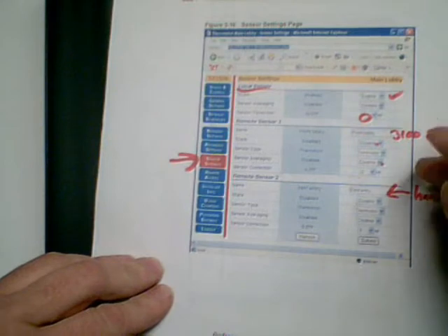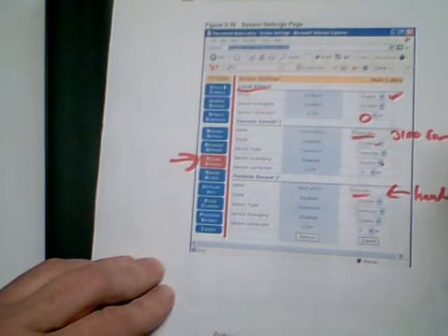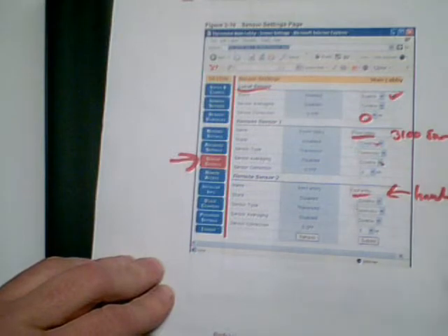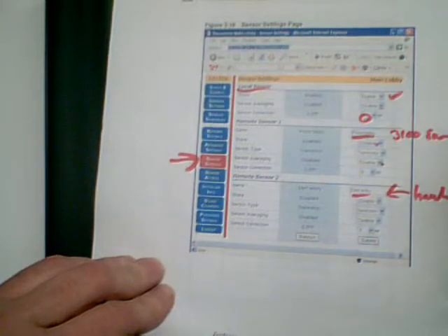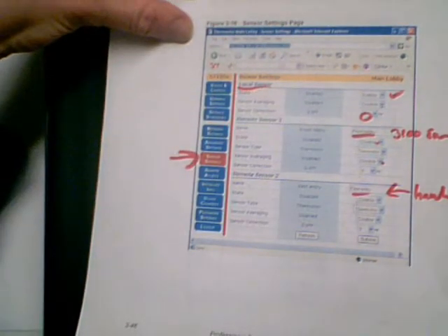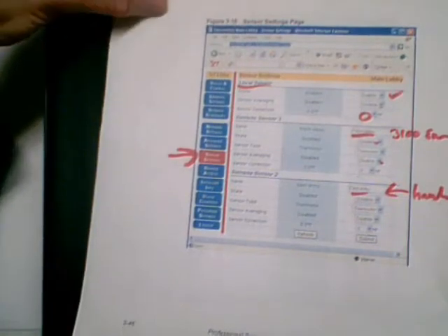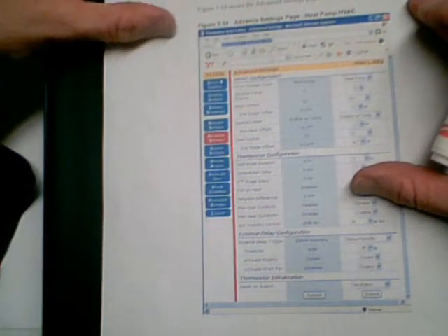These also show up on the main page. Whatever you put in here is the wording it uses on the main page, and will actually say front lobby, and then like 26 degrees or what have you. So if you look at the office thermostat, you'll see right on there, both on the display of the unit itself and on the web interface, you'll see outdoor temperature, and that's that probe that's sitting outside that is ultimately going to be used for the boiler as a lockout mode for energy savings purposes, but we'll be going to that later. Okay, the advanced settings page, we're going to go through this quickly.